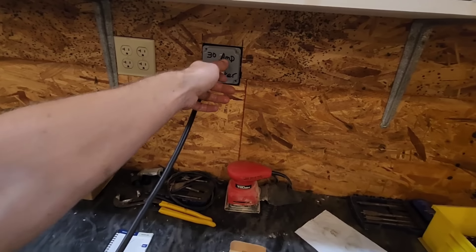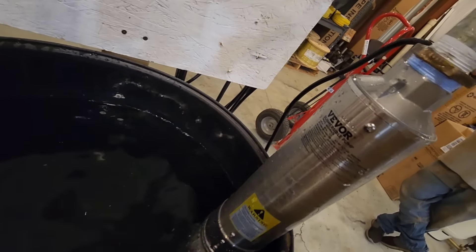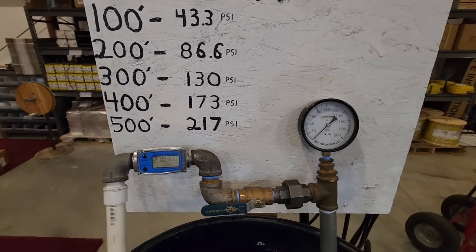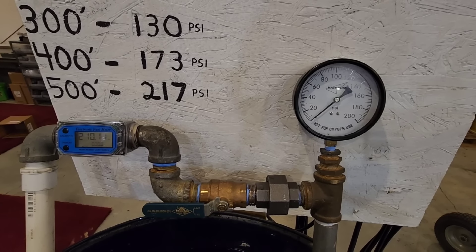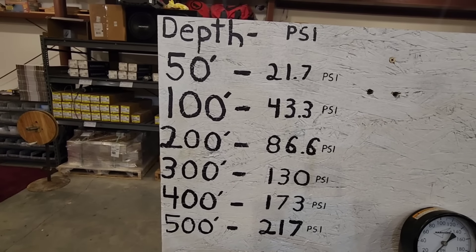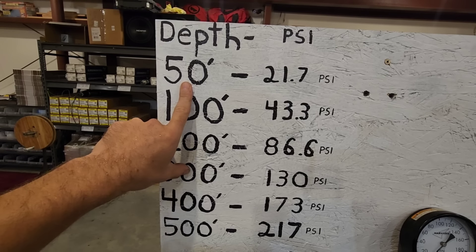We're going to go ahead and open this up, turn it off, and talk about it. So for full transparency, let's pull this out. This is the VEVOR well pump, half-horsepower. Its maximum capability was 74 — we'll call it 75 PSI. Now if we look at our chart here, it takes 21 PSI just to lift water from 50 feet deep. Now you have a pressure switch — a 40-60 or a 30-50 pressure switch.